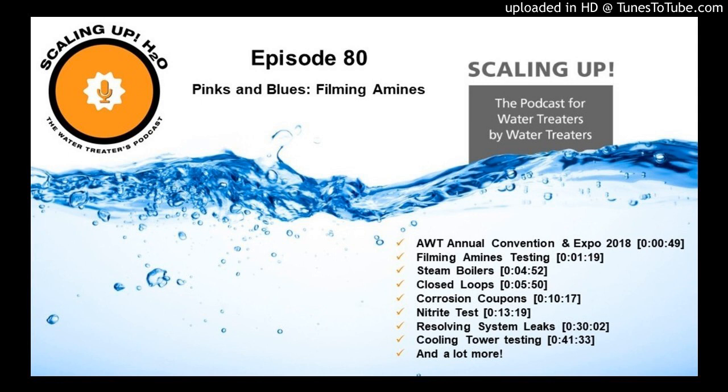And as you are probably asking, well, Trace, what about the PTSA that you blended in the product? Well, very close to the start of our test, we learned that Filming Amine and PTSA do not play well together. The way everything was blended into the system by weight, by math, when we had 3,000 ppm of product in the system, we should get 100 parts per billion of PTSA. Well, folks, when we put 750 parts per million of our Filming Amine product into the system, we were well over the limit of our fluorometer, and I believe that goes up to 330 parts per billion, and it was way over that range.